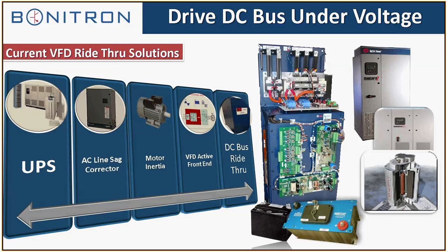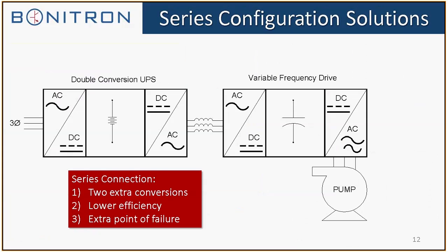There are other ride-through solutions: UPS, AC line sag correctors. Drives have some ride-through features, but it's usually cycles, and it doesn't cover enough to handle some of the utility power events you deal with. There are also active front ends, which give you a little bit of ride-through, but in a lot of cases it's not adequate to cover the specification. And then there's the Bonitron DC bus ride-through, which is what we provide.